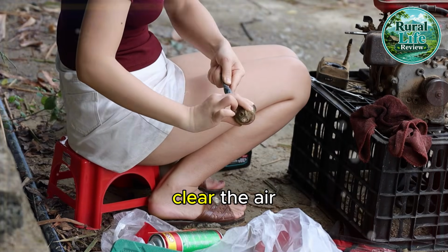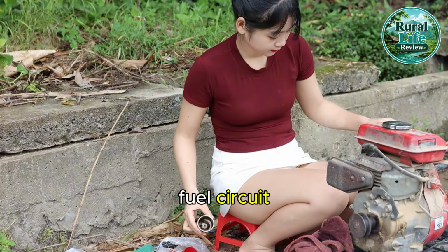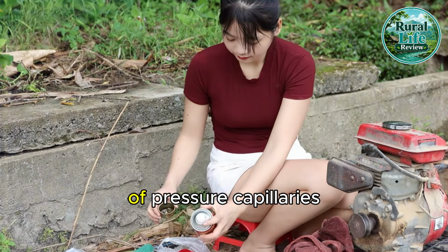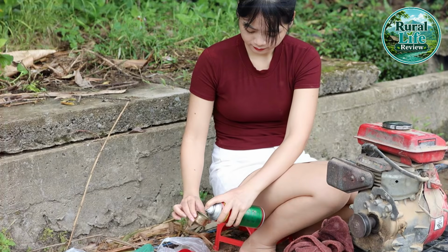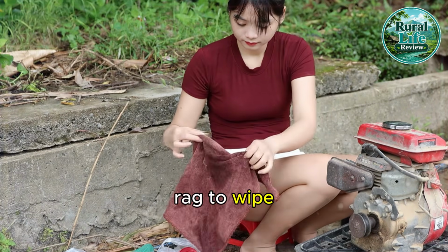Continue spraying to clear the air vents and the pilot fuel circuit. The clearance of this system of pressure capillaries is vital. Use a clean rag to wipe the chamber dry.